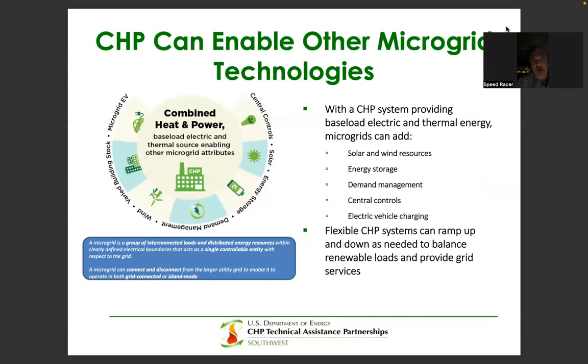A big recip engine or a combustion turbine gives very clean power, very robust, with good volt-var-frequency maintenance for the grid. It's rock solid, but it can take some time to respond to grid needs. A battery, an inverter-based system, is not synchronous without a signal, but it can respond very quickly, typically for a shorter period of time, depending on how many megawatt hours or kilowatt hours of capacity the battery has. It's not typically going to be anywhere near what a combustion engine can provide in terms of duration.